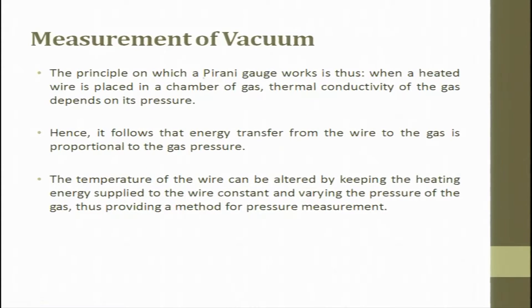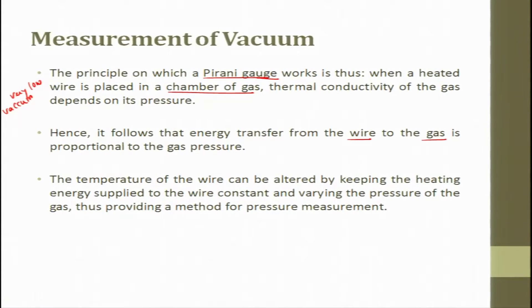The other gauge is called the Pirani gauge. The principle on which a Pirani gauge works is: when a heated wire is placed in a chamber of gas, the thermal conductivity of the gas depends on its pressure. Hence, energy transfer from the wire to the gas is proportional to the gas pressure. The temperature of the wire can be altered by keeping the heating energy supplied to the wire constant and varying the pressure of the gas, thus providing a method of pressure measurement.